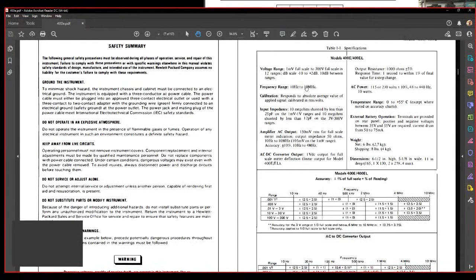So the AC output gives 150 millivolts RMS for full scale meter. What's its impedance? 1 volt DC for full scale meter. 10 mega ohms, it's right above you. 10 mega ohms shunted by less than 25 picofarads. Yeah, you can tell I'm an old timer, I say puff. That would be the main limiting factor for frequency, along with other parts of the circuit.